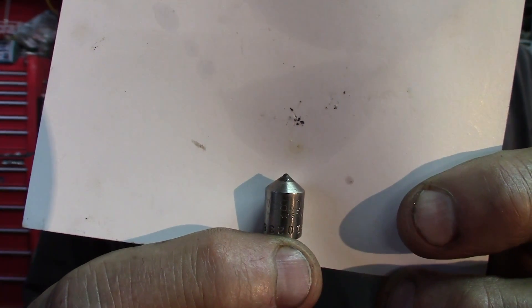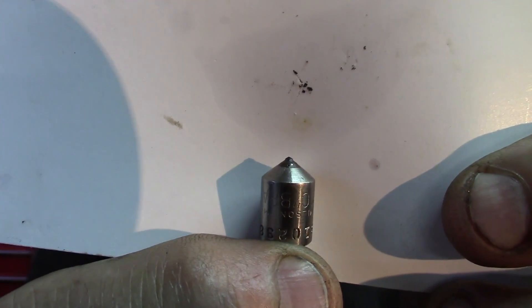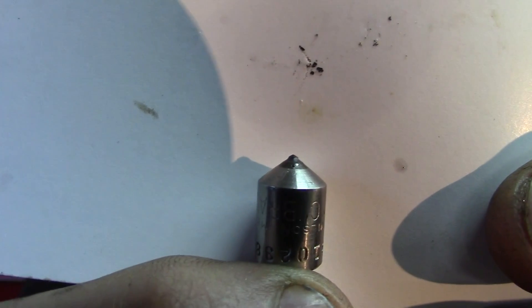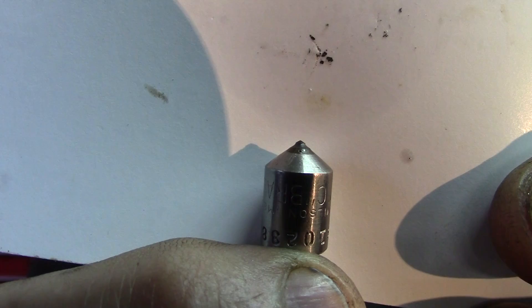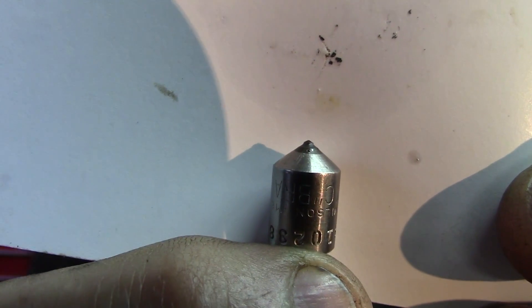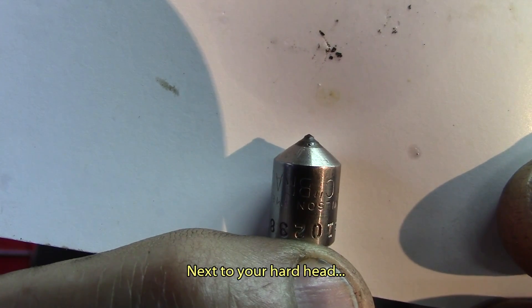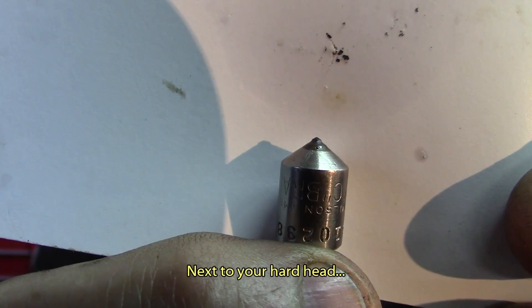Here's a close-up of the diamond Rockwell indenter we're using. It has a nicely conical shape and is made from diamond — one of the hardest materials on earth — which is what allows it to penetrate into the steel.